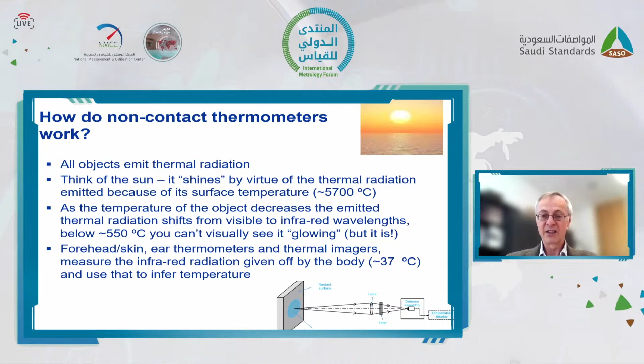These thermometers work by measuring the thermal radiation that's emitted from surfaces. So the sun's surface is about 5,700 degrees Celsius, so it shines by virtue of its temperature. As the temperature goes down, the emission shifts into the red and then the infrared. Below 550 degrees Celsius, you don't see it glowing anymore, but the surface is still glowing, in the infrared. And these forehead and skin thermometers, infrared thermometers, thermal imagers, measure that emitted thermal radiation and use it to infer a temperature.